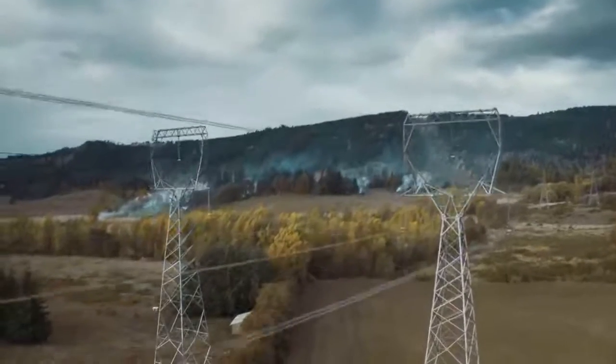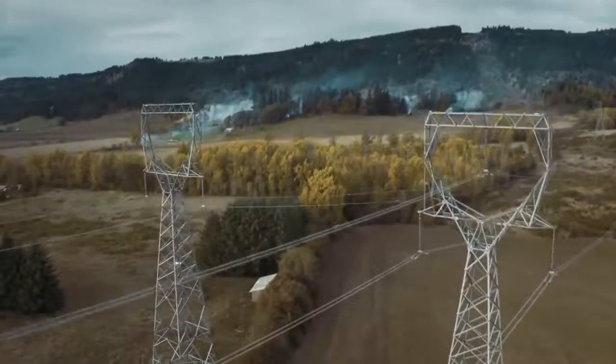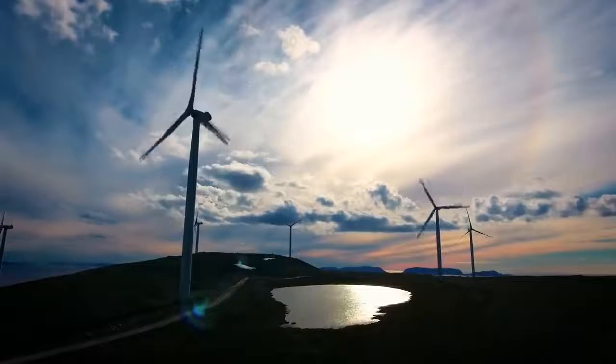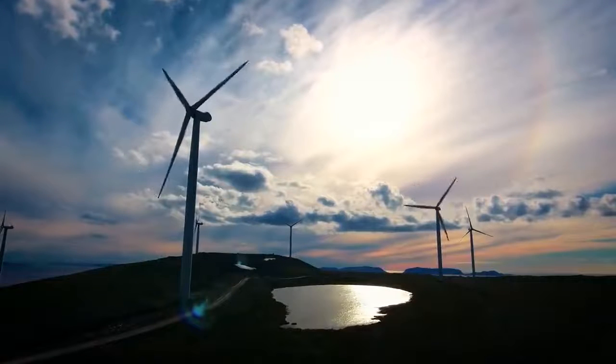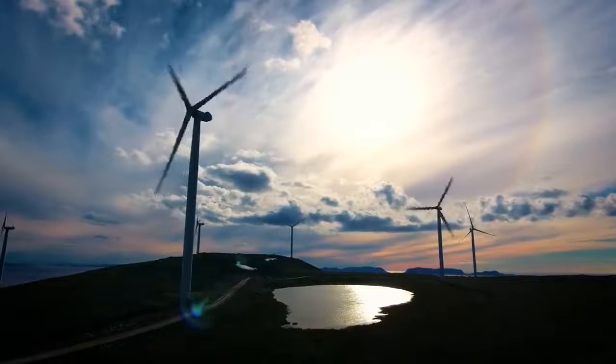Electrical demand is felt immediately by all the connected generators. Each additional demand causes a little more load on every generator together, slowing the rotation by just a tiny amount and thus decreasing the frequency of the alternating current. Similarly, if electricity generation exceeds the demand, the generators will speed up.